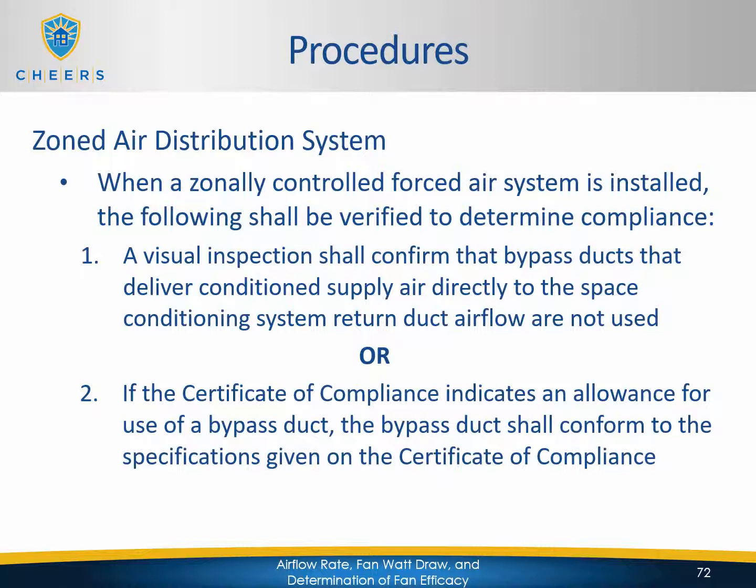If they're not supposed to be used but they're present, it will be a fail. If they are supposed to be used but they're not present, it will also be a fail. So you have to visually verify whether they are there or not and install to standard depending on what the CF1R states.